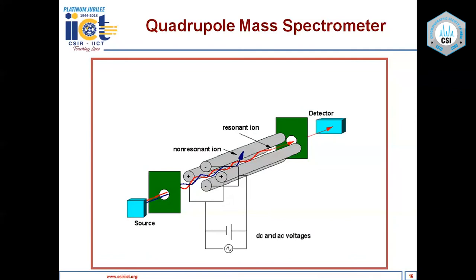In quadrupole mass spectrometers, ions are analyzed by a quadrupole field produced by four hyperbolic rods placed at the corners of a square. Adjacent rods have opposite polarities, and a combination of RF and DC voltage is used to mass-separate the ions. At a particular ratio of RF to DC voltage, only ions of a specific m/z value have stable oscillations and pass through the collector slit to reach the detector. Other ions strike the walls of the rods.